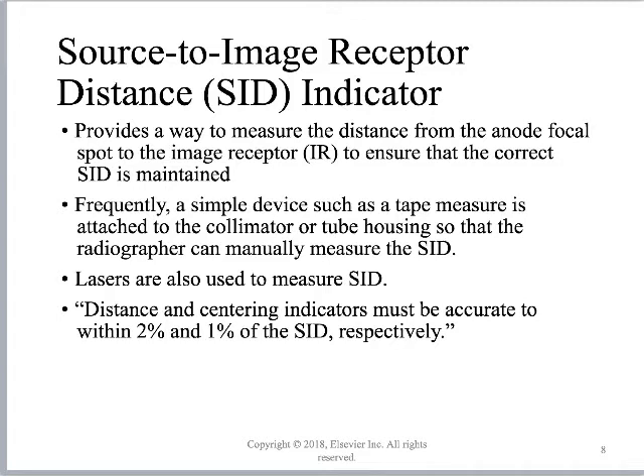If you just remember it's the same percentage as milk — 2% and 1% — you should be okay. They're interested in a range of numbers, and you have to dig into government documents to find where this FDA regulation is at. The 2% coincidence means the light field should correspond to the actual x-ray beam to within 2%.